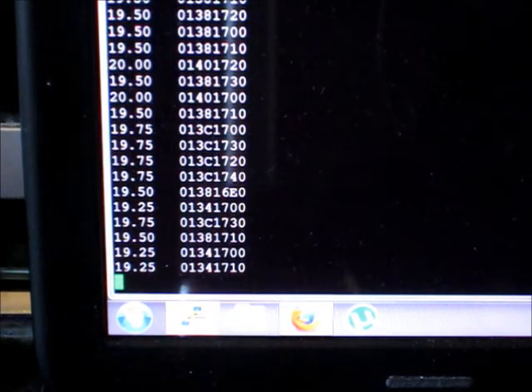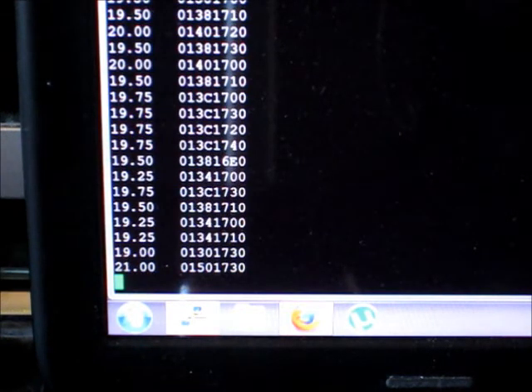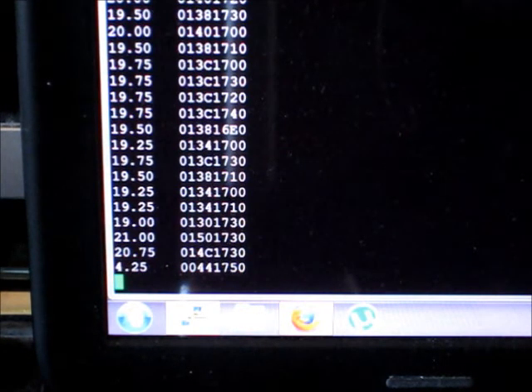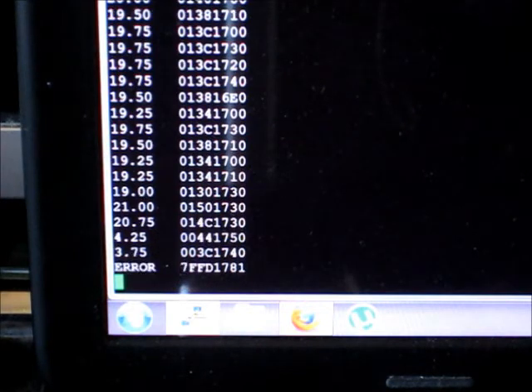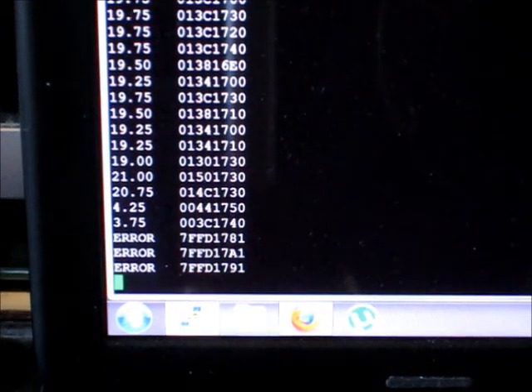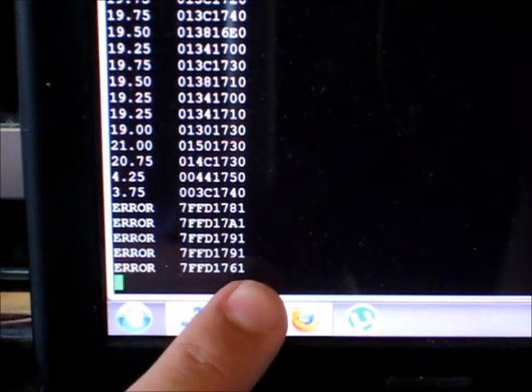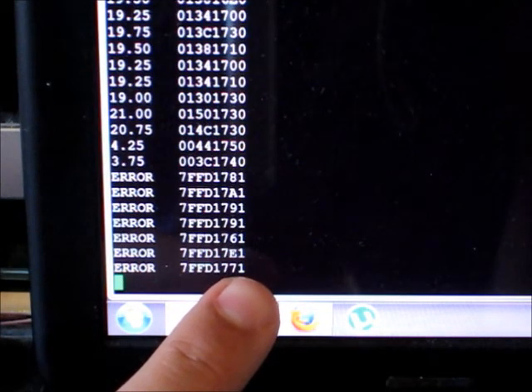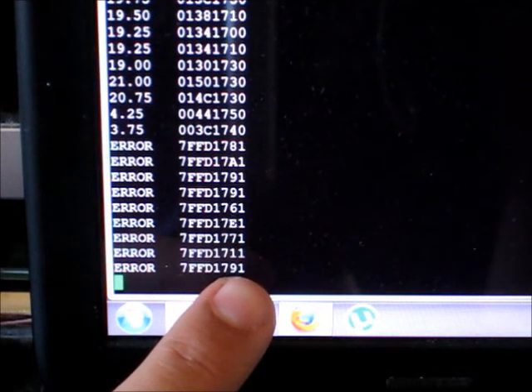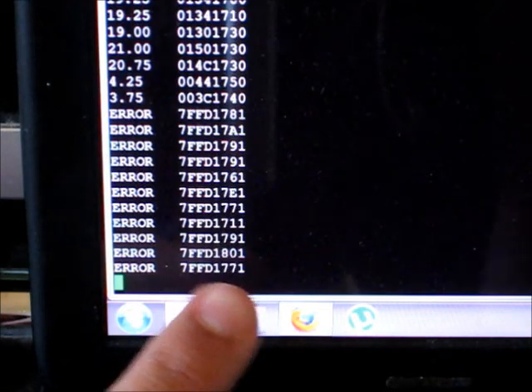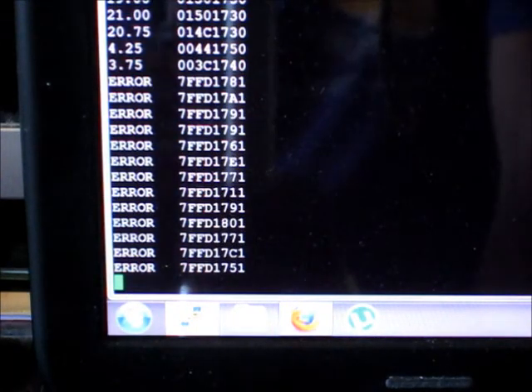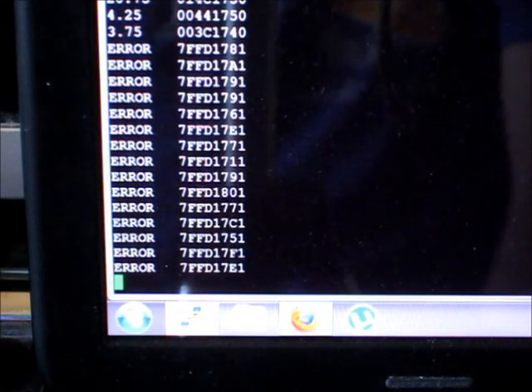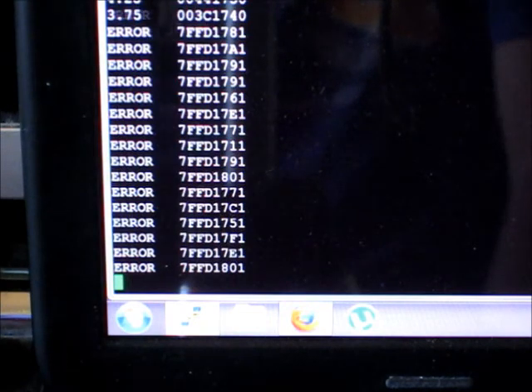And so if I were to unplug the thermocouple right here, you would see that it would go into an error state. So now it's saying error, because the thermocouple is disconnected, which is error code 1. Error code 2 and 4 is it also checks for the thermocouple being shorted to ground or to VCC, which would start giving you wrong numbers.